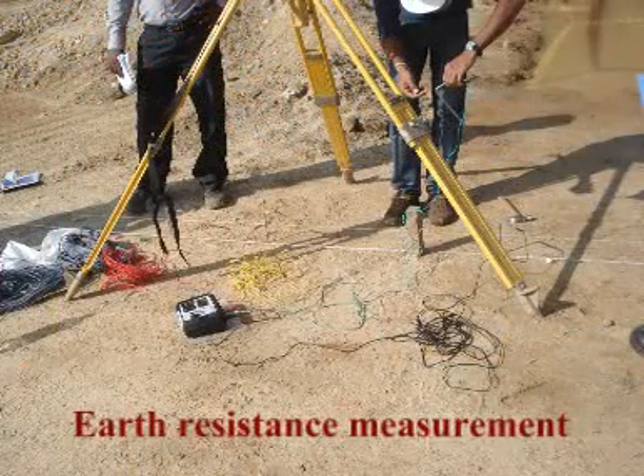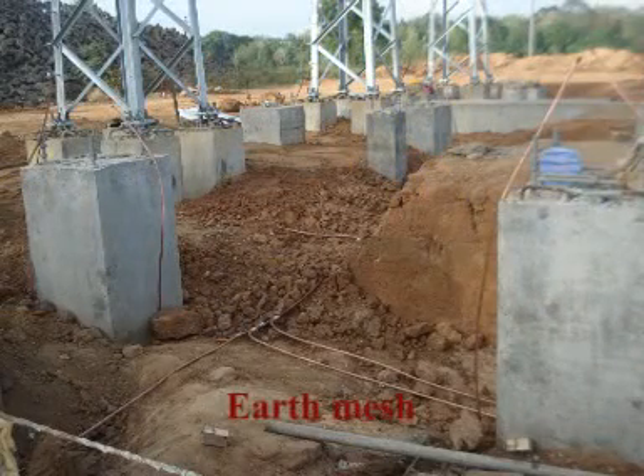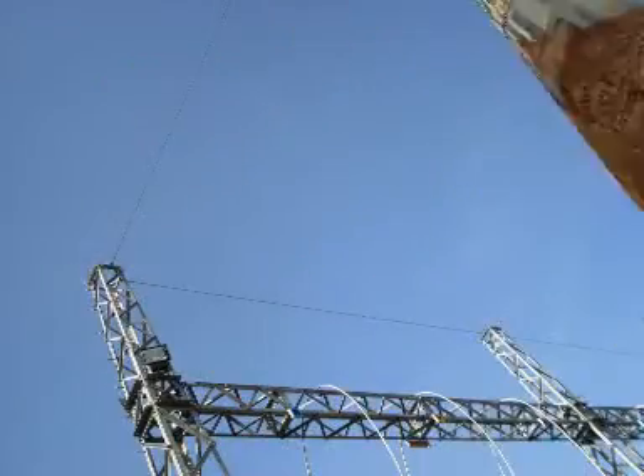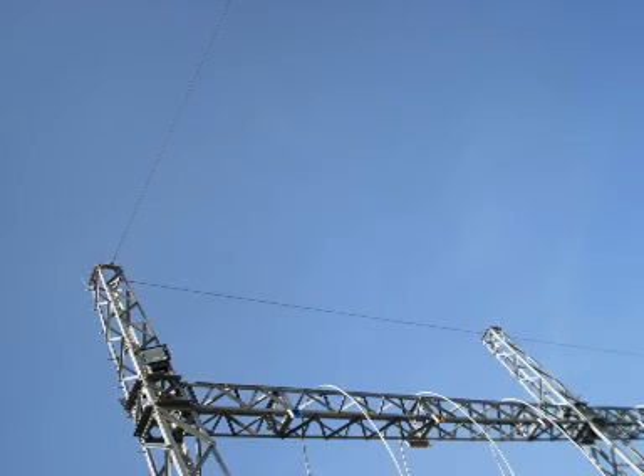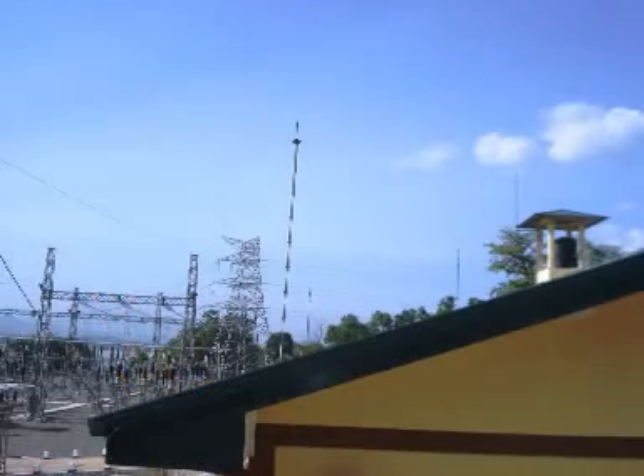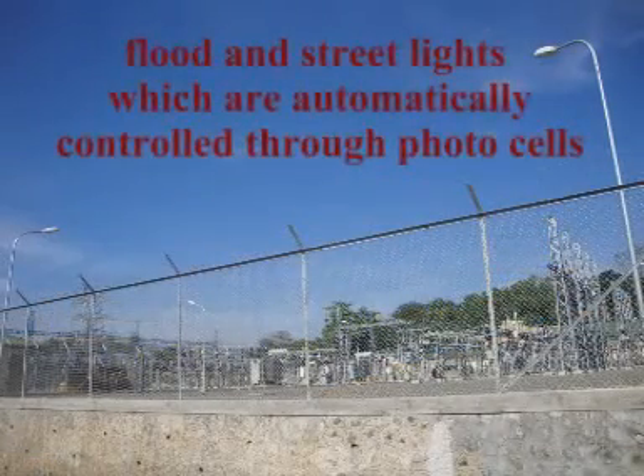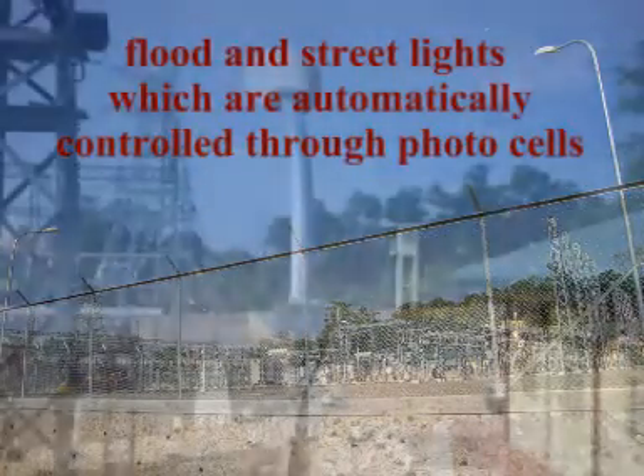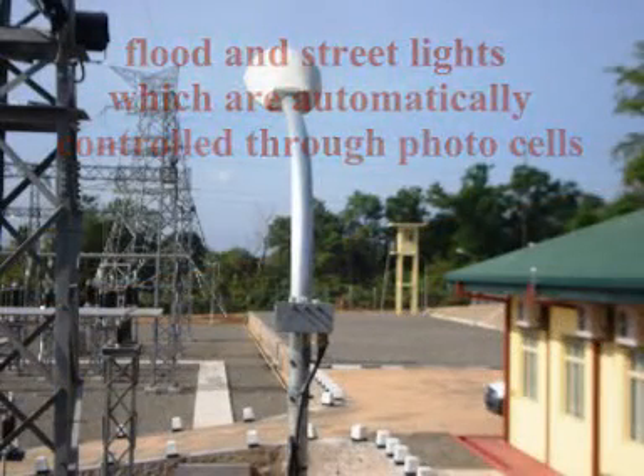All equipment and steel structures are properly earthed through an underground earth mesh. Also, overhead lightning shield wires are provided to protect outdoor equipment from external lightning strikes. The switchyard premises is lit by flood and street lights, which are automatically controlled through photo cells.